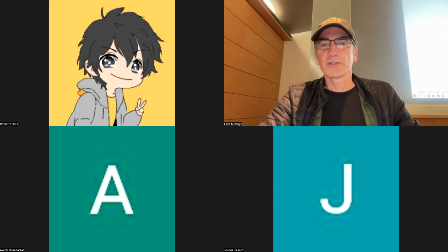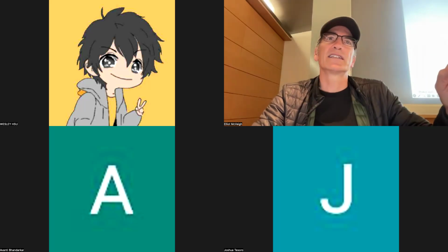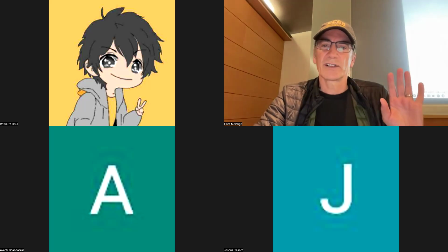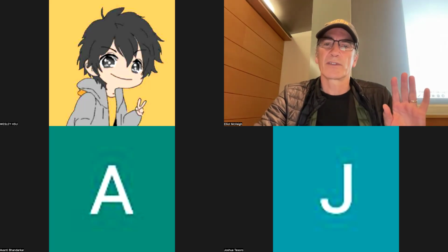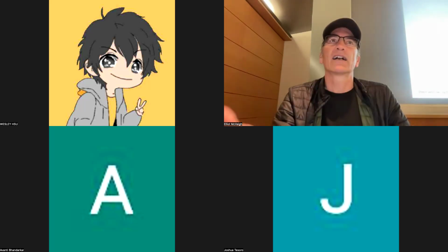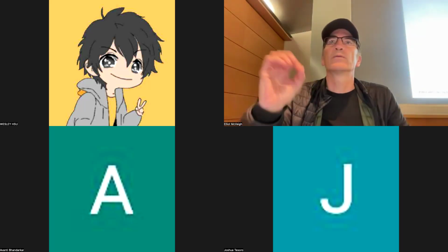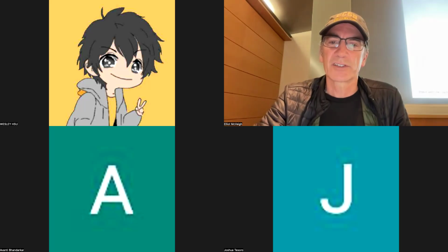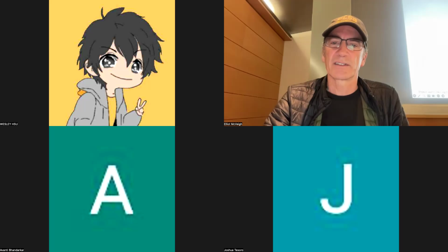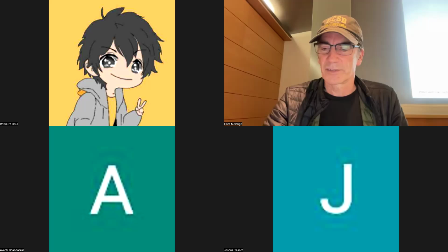Let's do a quick review. In CT, if I put a tiny little metal bead in my CT scanner and take a picture, in just one dimension, it comes out with some function that I can characterize. Normally, I write down something like a Gaussian, and then I have an analytical description of what a bead will look like in my images. That's also called the impulse response function, because this signal here is essentially a point or an impulse.